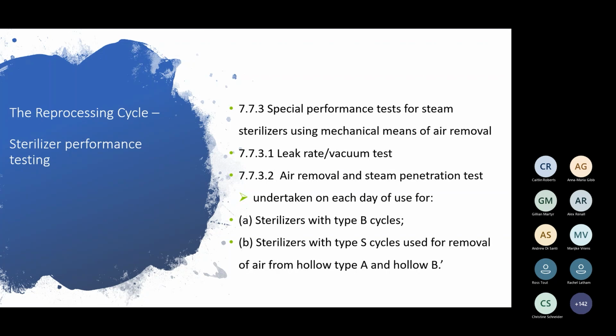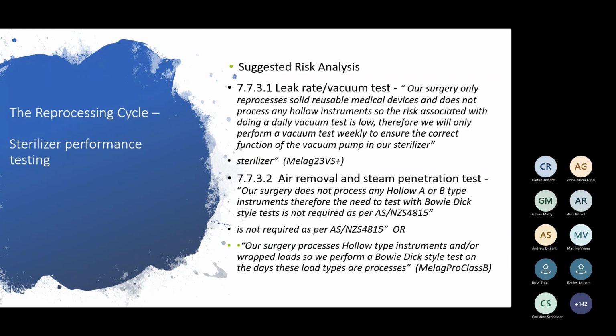An air removal and steam penetration test, which is a Bowie-Dick test, should be undertaken on each day of use for sterilizers with B class cycles. So that's your hollow instrument. Sterilizers with S class used for removal of air from hollow A and hollow B. If you don't process hollow instruments, then you don't need to be doing the air removal of the Bowie-Dick test. So suggested risk analysis is around this.